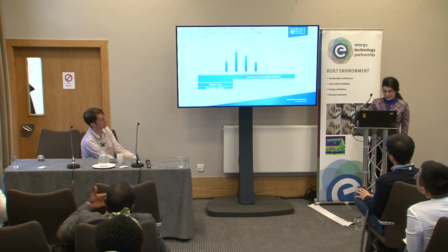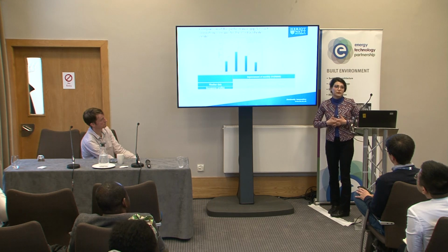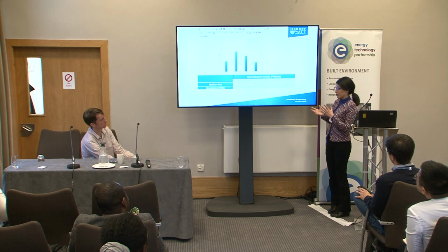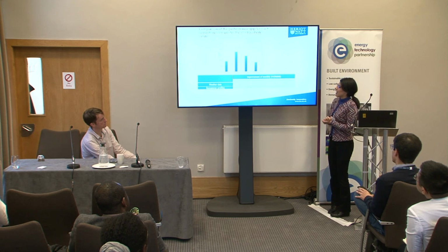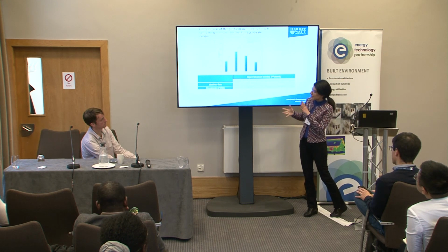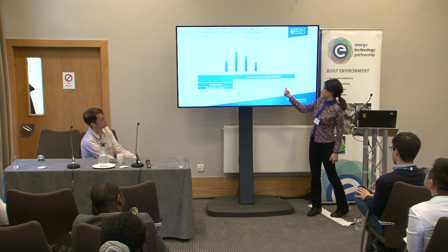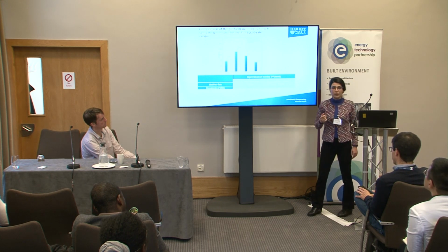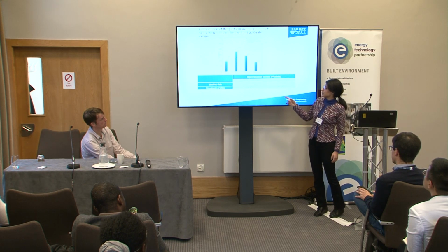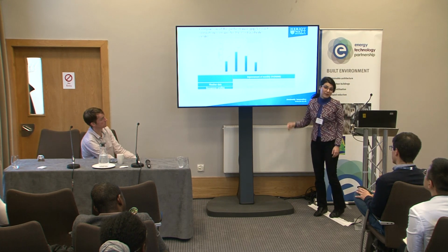For the postgraduate center, because I had the meter data available, I was able to study the impact of occupancy on the performance gap. And as I've shown in this table, using database occupancy profiles has led to 9% and around 12% improvement of performance gap for gas consumption and electricity consumption, which is more significant compared to the impact of weather data.